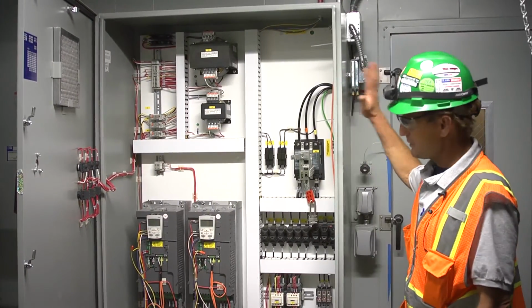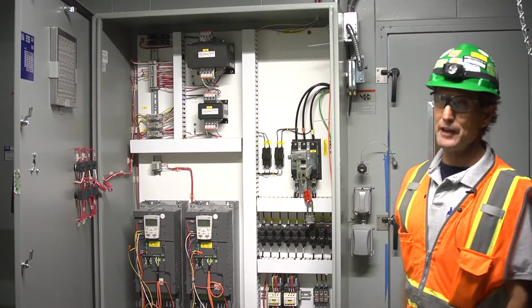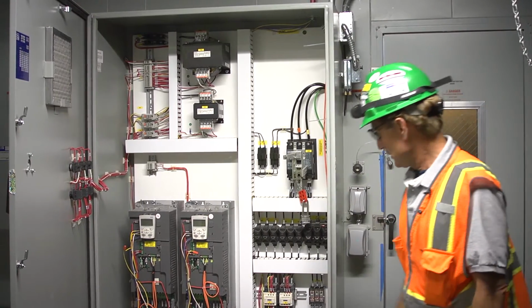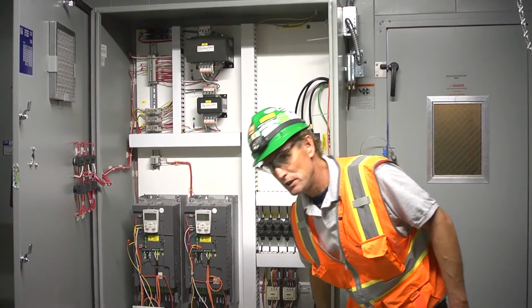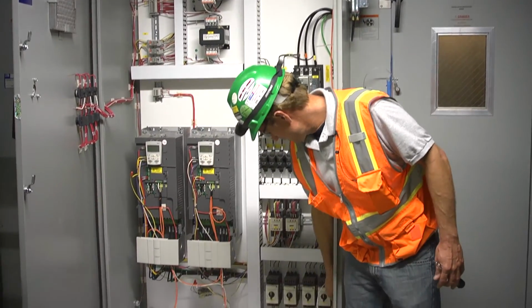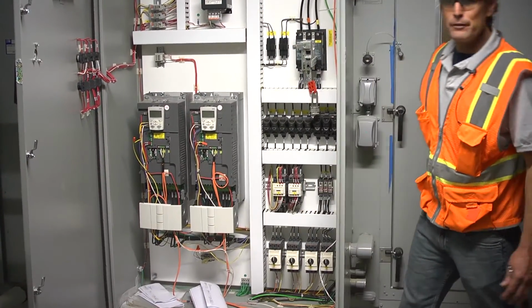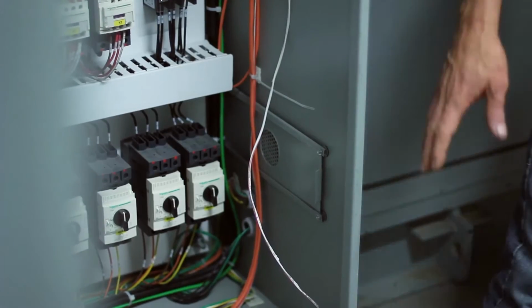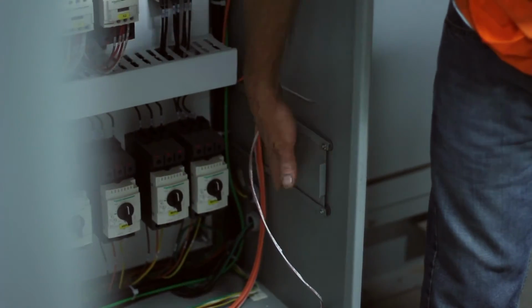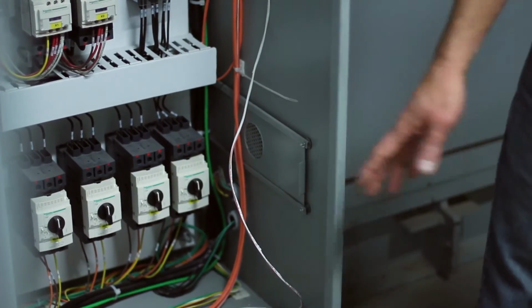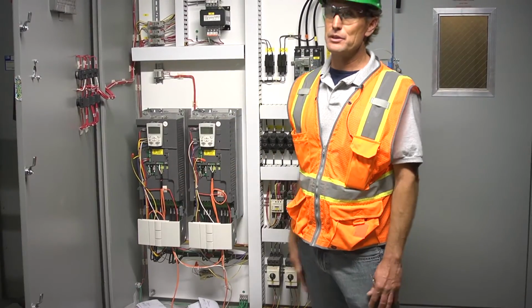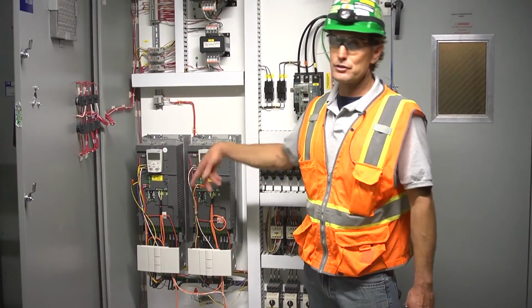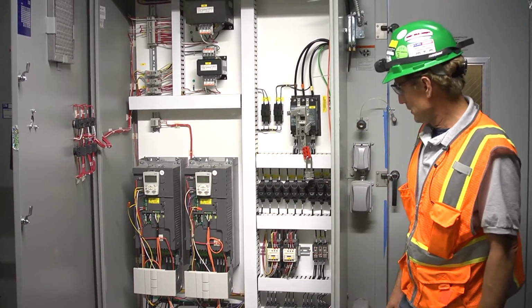So this panel, again, is single source power for the unit, and the supply fans are in this cabinet. Lastly, on the side of this unit, there's a vent right here that provides cold air from the discharge of the air handling unit to cool the cabinet. So this should always have cool 55, 60 degree air coming in from the unit to cool the VFDs, which have their own circulating cabinet fans within them to keep air circulating through the VFDs.